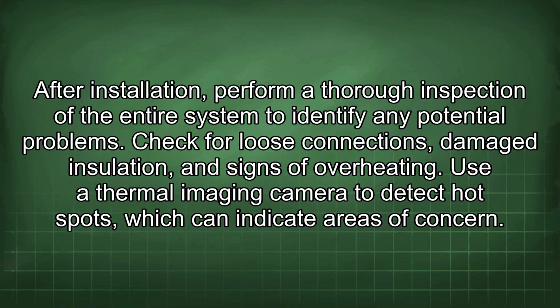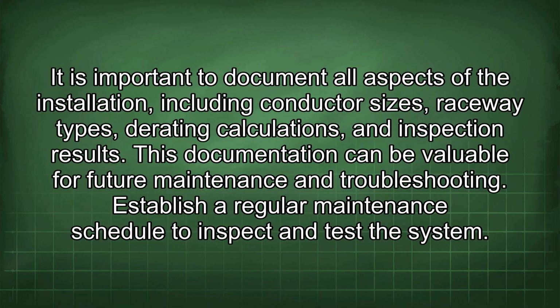Check for loose connections, damaged insulation, and signs of overheating. Use a thermal imaging camera to detect hot spots, which can indicate areas of concern. It is important to document all aspects of the installation, including conductor sizes, raceway types, derating calculations, and inspection results. This documentation can be valuable for future maintenance and troubleshooting.